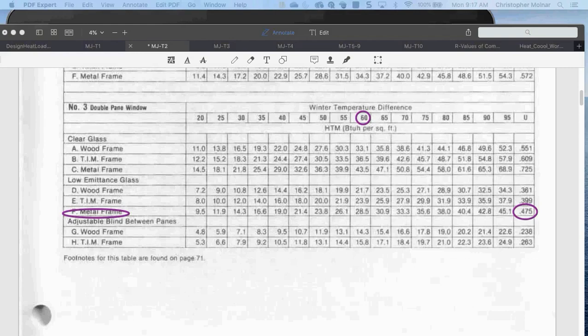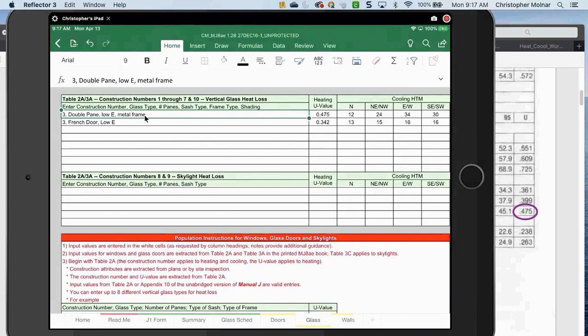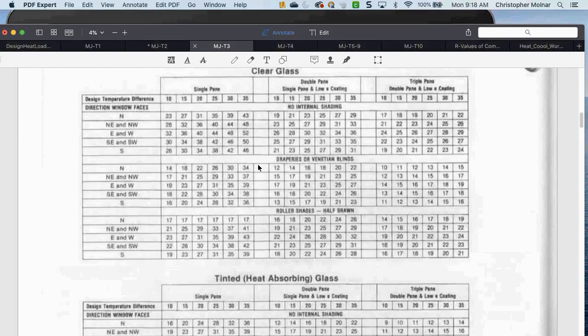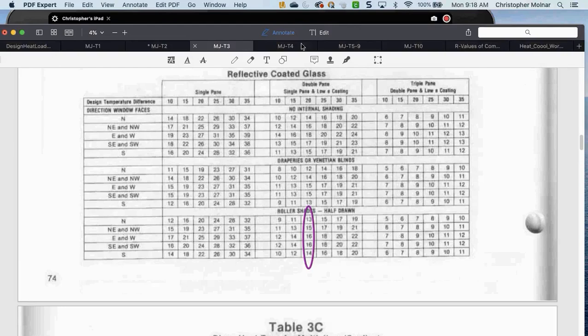Back to my glass sheet. What you're doing here is for this type of window — at this point you're not worried about individual windows. You're entering the U value, and then you're entering the cooling HTM from Table 3, based on what type of glass you have. For example, double-pane plate with low-E coating, you're using values of 13 or 15 based on directions. At this point, we are not worried about individual windows — just construction on the glass tab.